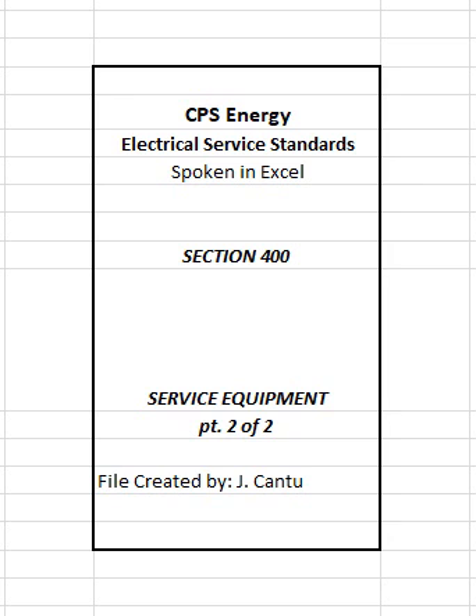406 Maximum number of disconnects. The service disconnecting means for each service permitted by the NEC and in accordance with the limited special conditions outlined by CPS Energy in section 200, shall consist of not more than 6 switches or sets of circuit breakers, or a combination thereof mounted in a single enclosure, in a group of separate enclosures or in a switchboard.